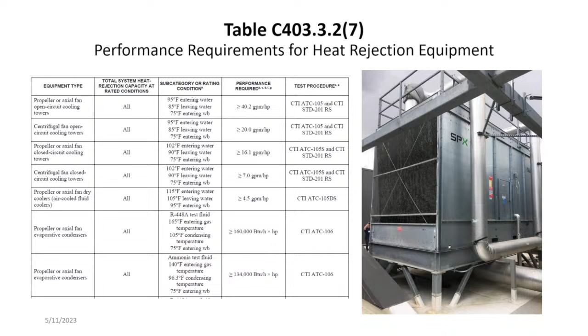This is the same cooling tower that we can use for that free indirect cooling, because we have the pads that we get all saturated with water. We flow air through it. Evaporation is a cooling process. We can drop it 20 or 30 degrees, take that evaporatively chilled water in and circulate it through a separate coil, and we get indirect free cooling. All we're using is a little bit of pump and fan horsepower.